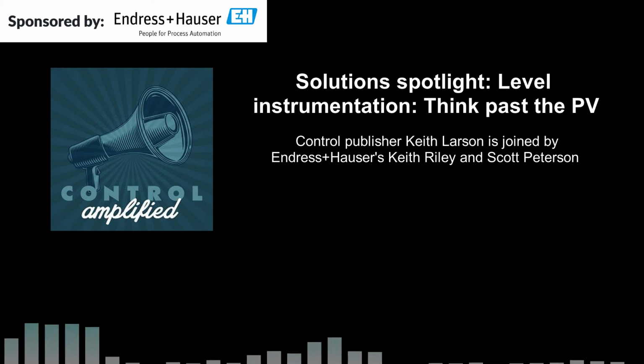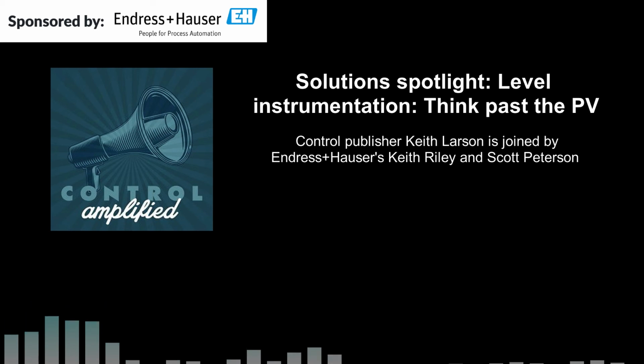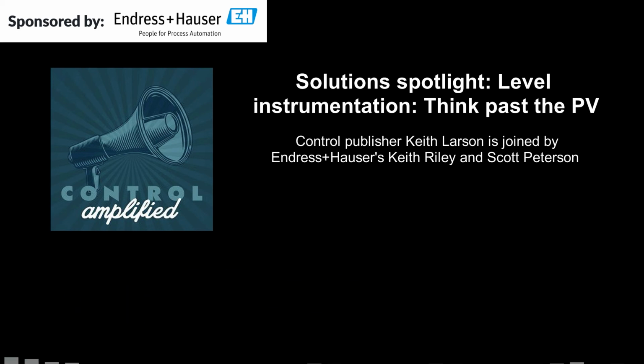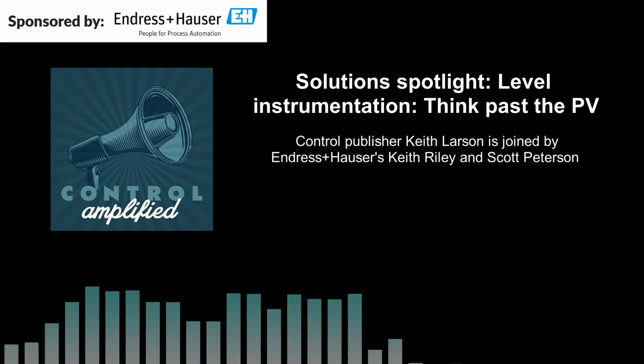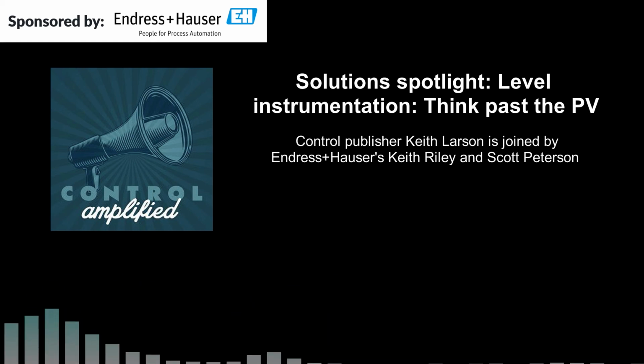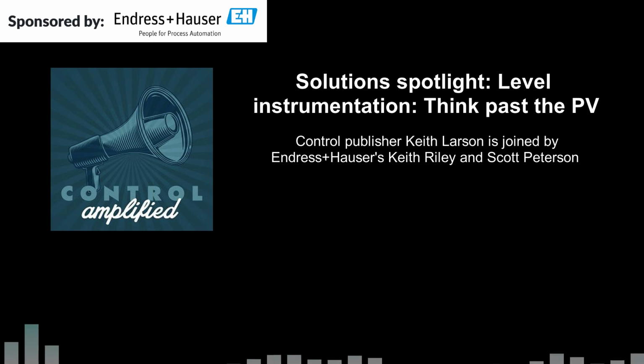Instead of everything being reactive, you're being preventative or forward thinking about when you have to get out and deal with it. The last one is what I'm going to call verification, and I'm careful with that. I'm not talking calibration. I'm talking verification of the device, which is a quantitative assessment, not a qualitative assessment. And for most of the Endress+Hauser instruments with this capability, you're doing a check of the electronics. You're gauging it against the specification of those electronics when the instrument was new, and it's telling you, yes, it's still within spec. No, it's not. But the nice part about that is once you've done that with a high percentage of total test coverage, well into the 90th percentile, you have a high degree of confidence that the unit's still working. So that's a great, put your mind at ease, I guess is the best way to put it.